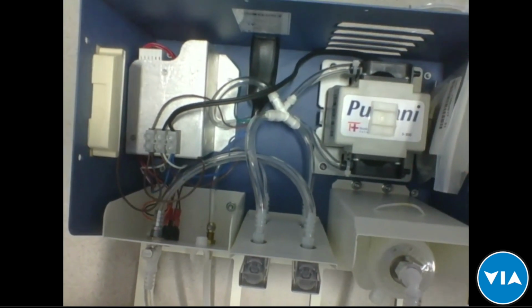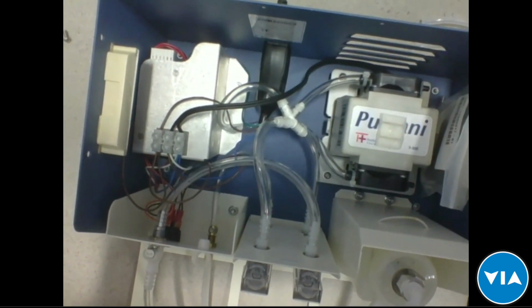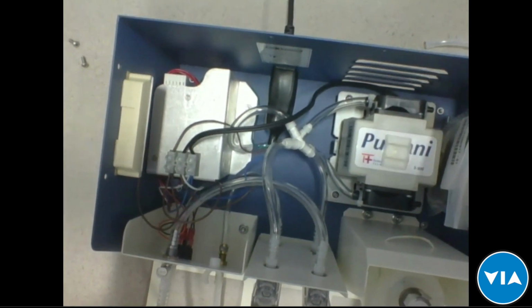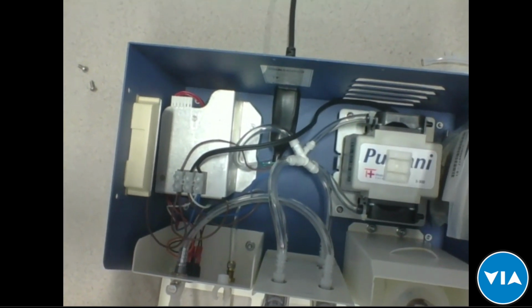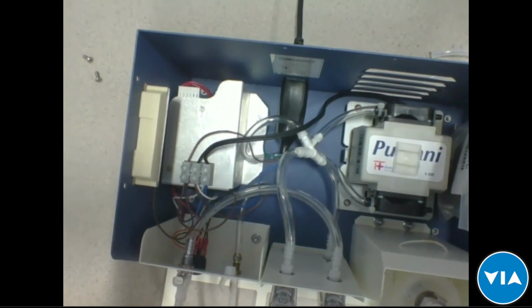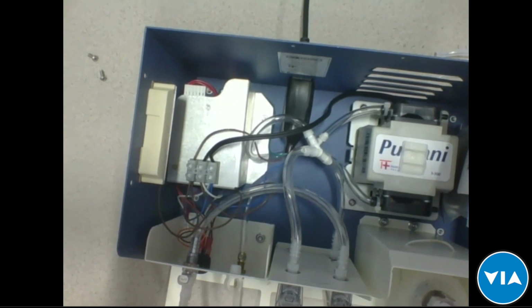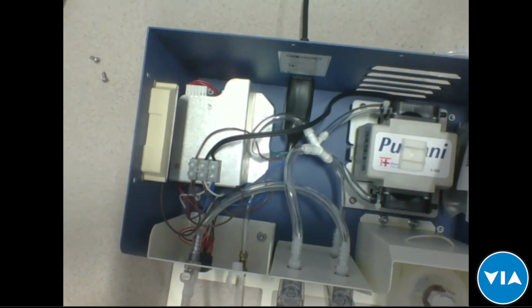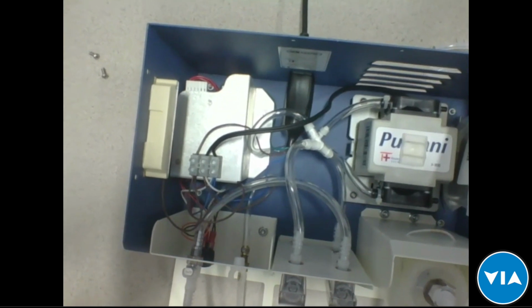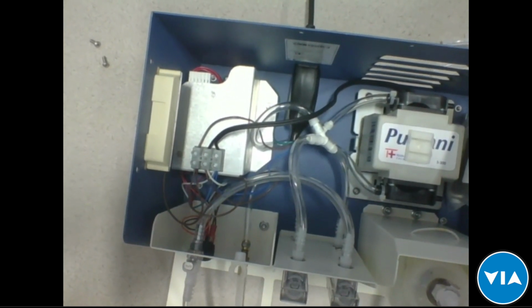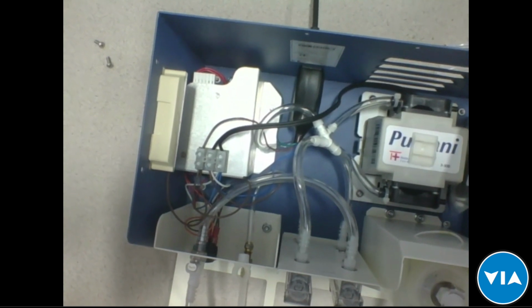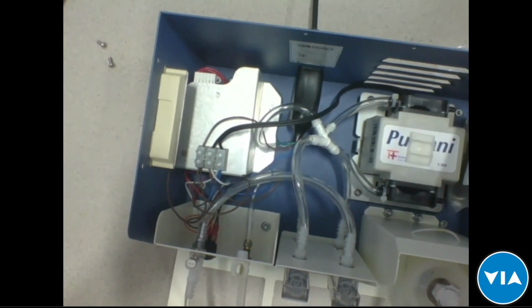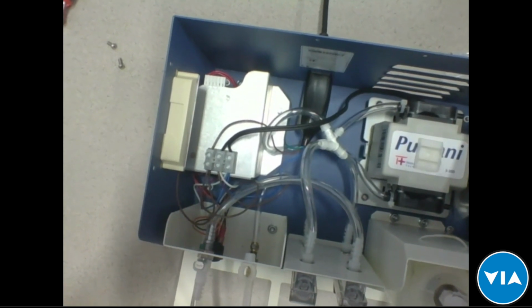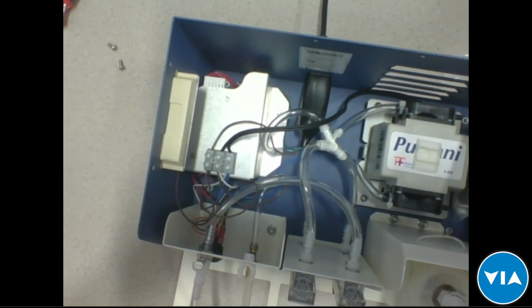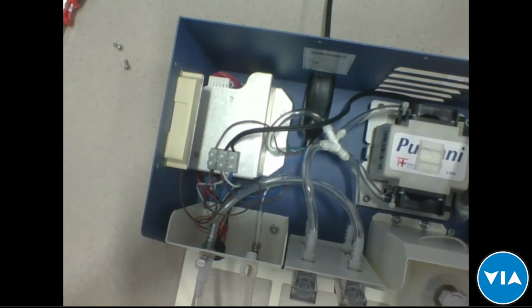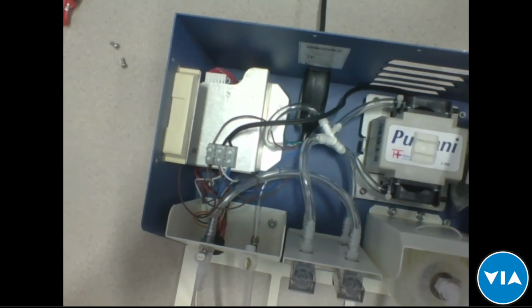There is also, I think you have it on your site, Brian, a diagram that shows the different tubing pathways, and they're colored. It can show this a bit clearer, as well as a troubleshooting video that shows you exactly what to do for this problem. And if there was another problem that would cause that same thing, it could be just a dirty bead inside the flow meter. But I think that there's a diagram and video in there that will show you exactly what it looks like when it pops off. But don't be afraid to open the machine, check to see that everything's connected, and put it back on.